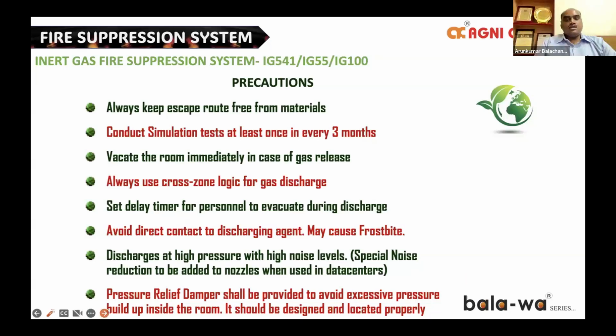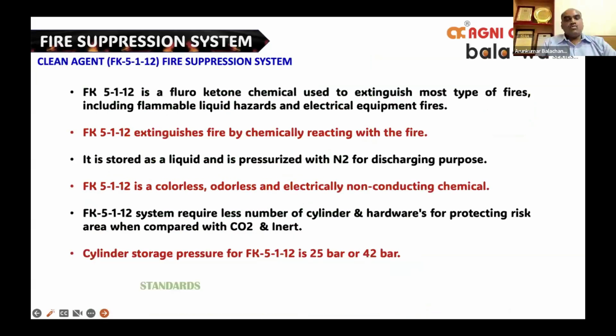We'll now move to the next system, which is a clean agent or chemical agent system of FK5112. FK means fluoroketone. Fluoroketone is a chemical manufactured specifically for fire suppression purposes. Unlike the inert system, which displaces oxygen, the FK chemically reacts with the fire. It is a chemical reaction. It chemically reacts with the fire, and thereby it suppresses and extinguishes the fire. FK is in a liquid format and it is pressurized with nitrogen for discharging purposes. The agent is a colorless, odorless, and electrically non-conducting chemical.